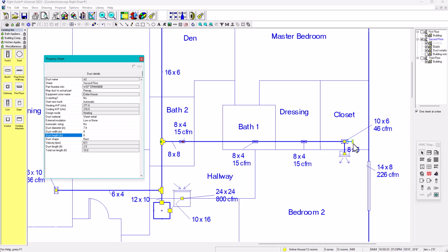Why? Because the height is 8. The height of this branch is 8. And for this register, the size is 8 actually. Yeah, this is not looking good, but depends on how they're connecting this actually. So if this is a branch and then they're connecting this register directly to the branch, that cannot be possible, because usually what we follow is, if the height is 8 in here of the register, right, the sidewall register, and the trunk height is 8, there is no space, right?